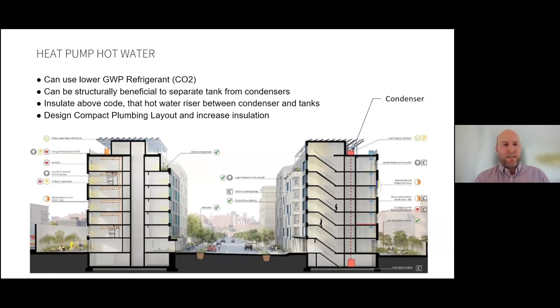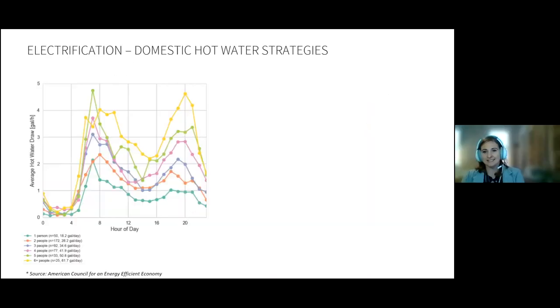Rachel, on Linden 2, you're advancing the system in construction, right? Yes. And also, one of the items to keep in mind for electrifying domestic hot water, as Joe mentioned, has been accommodating the peak load, actually. So this chart here shows a typical day's hot water use for a residential building. You have a big peak in the AM as folks are starting up their days, and then another peak later in the day as folks are cooking meals and getting ready for bed.